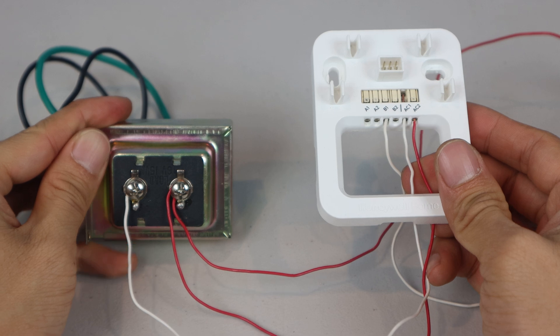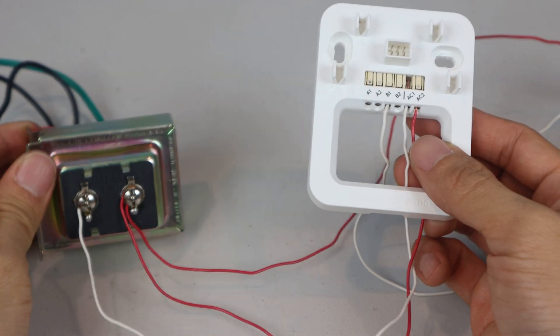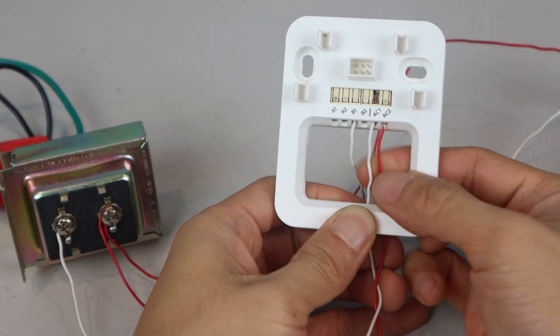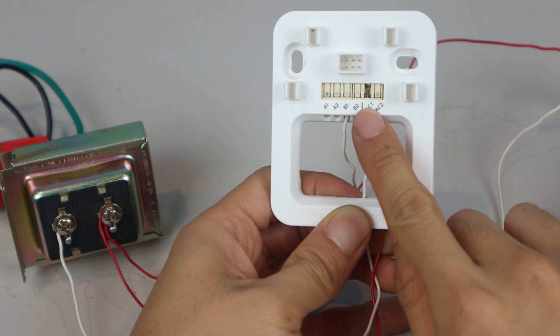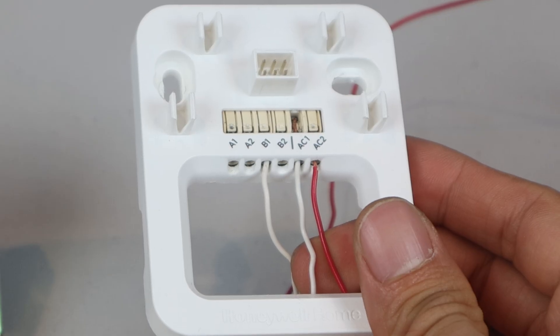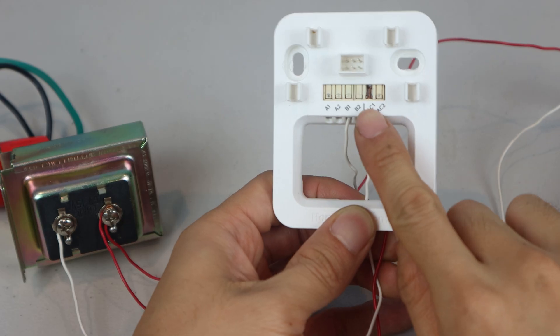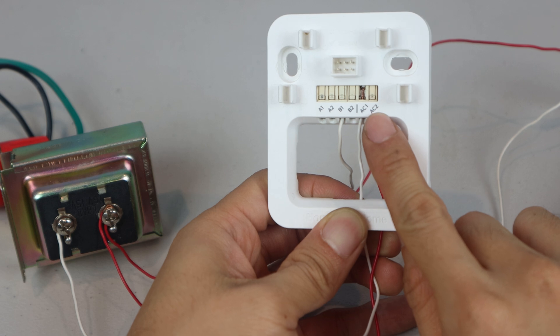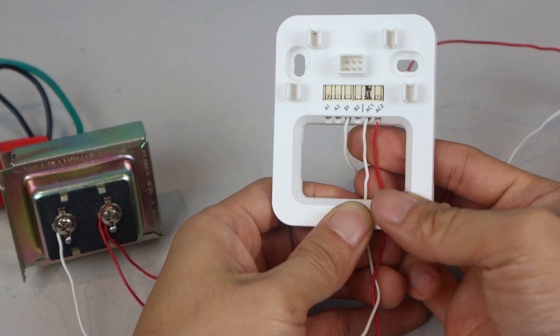One side of my transformer, which is 16 volt 15 VA, will be hooked up to the AC1 terminal. That's the white wire on the left, and on the other side of the transformer, there are two red wires. One of these goes to the AC2 terminal. So just remember that AC1 and AC2 are the ones that connect to the transformer.